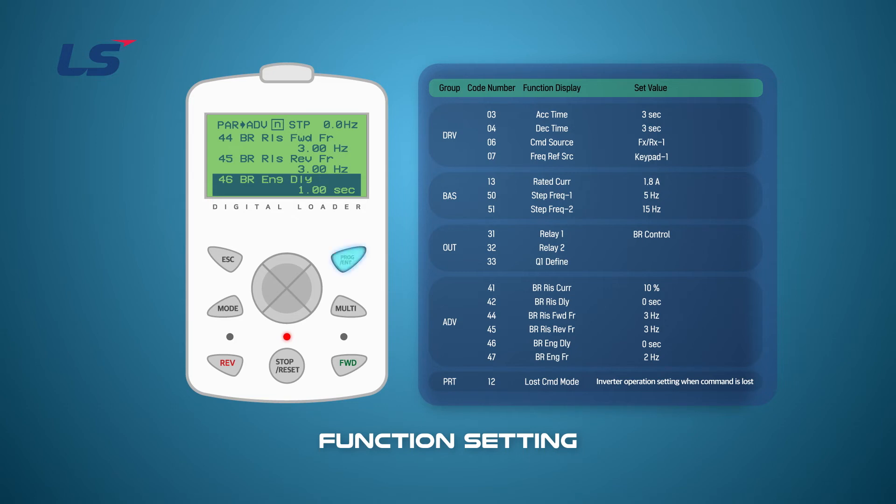In summary, the current is 1.8 amps when accelerating, the brake is open at 3 Hz, and the brake is closed when decelerating at 2 Hz.